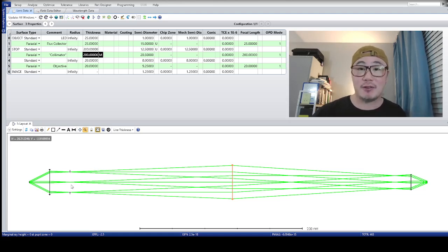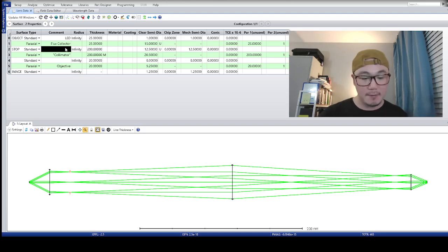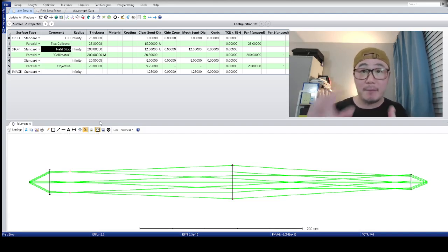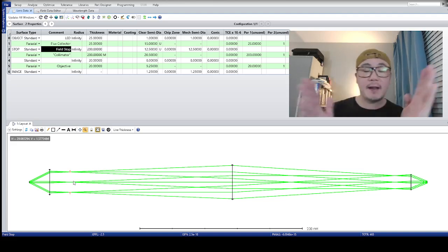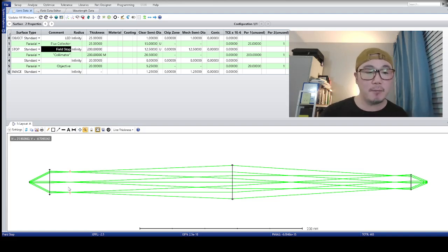this aperture, which, in the terminology of fluorescence imaging, we can call a field stop. You can call it a field diaphragm or a field stop, but it really is a physical aperture located at the front focal plane of this collimating lens. If you consider the left side the front and the right side the back, it's at the front focal plane. Therefore, the rays are collimated.